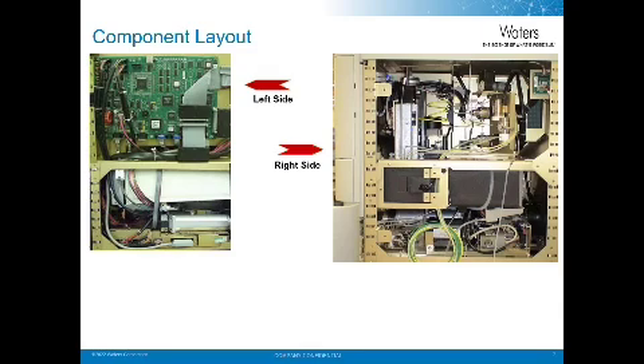We would also be able to see the syringe drive, the carousel drive here, the needle pump wash shown here, and then valve 1 through 4 is also in this general area, and we'll talk more about that later. In addition, we'll be able to see the loop here, this yellow loop, which is the 100 microliter loop. We will see the degasser assembly shown here. So here we have the degasser chambers, our GPV valve down here.